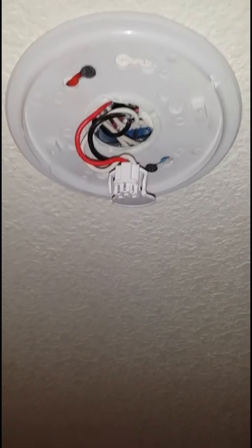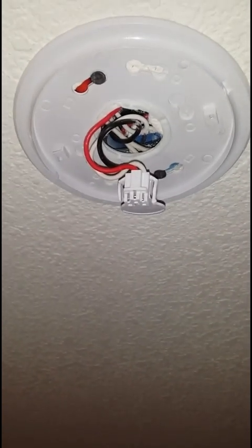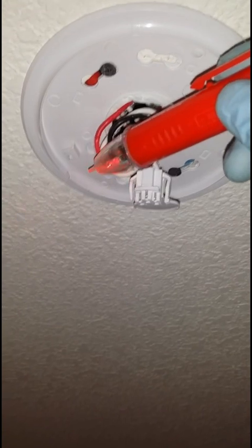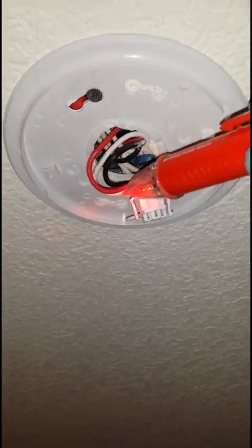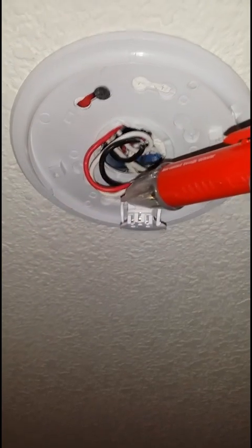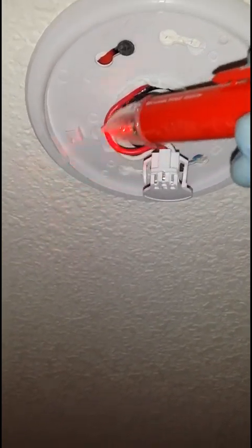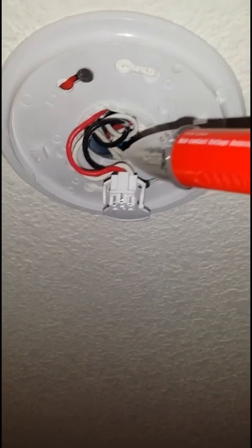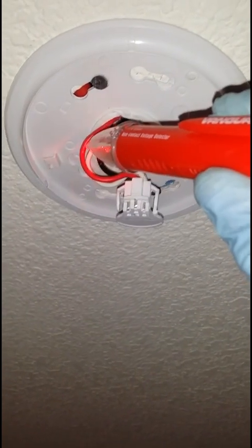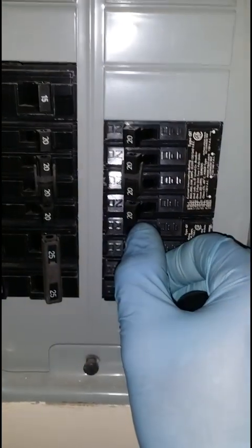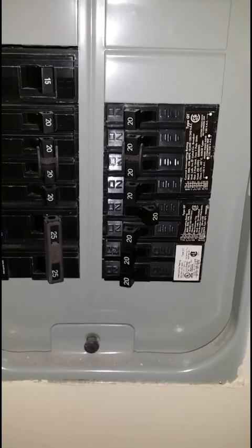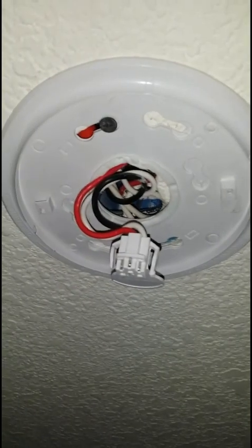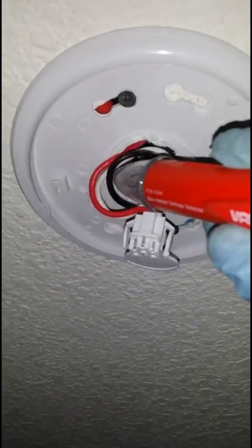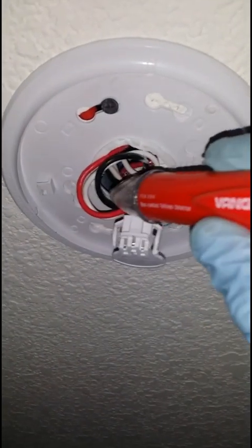Now we are going to take our voltage detector and make sure that we do have power coming to the line. So you see here, I do have power coming to this line. You want to make sure, before we do anything in replacing the wire and the base, that we disconnect the power from the circuit breaker. You turn the breaker off. You'll go and test it and make sure that there is no voltage coming through. Now we're going to take our non-contact voltage detector, make sure it's on, and you can see here that there is no power coming through.